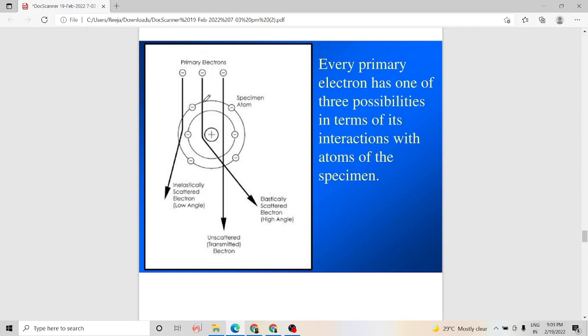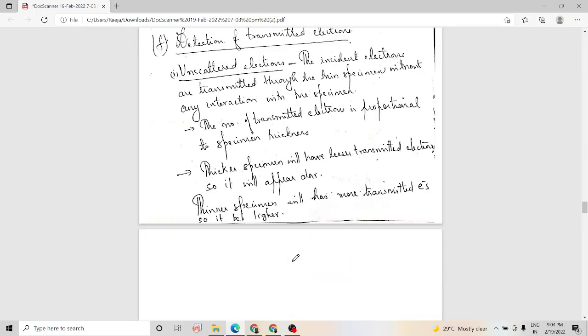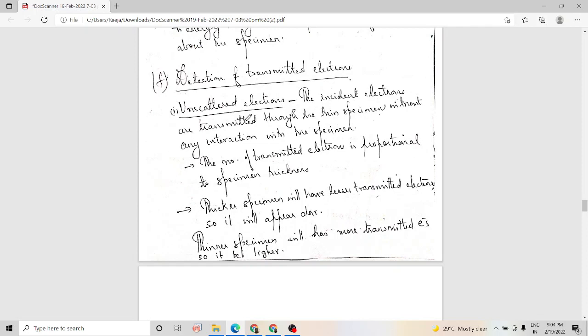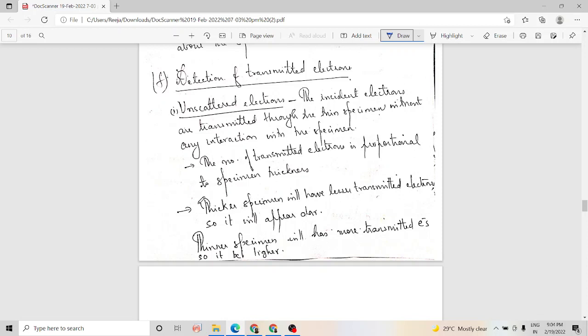Next, we discuss transmitted electrons. When the primary beam of electrons transmits through a specimen, it can go unscattered, elastically scattered, or inelastically scattered. In the first case — unscattered electrons — the incident electrons are transmitted through the thin specimen without any interaction. The number of transmitted electrons is proportional to specimen thickness: thicker specimens produce fewer transmitted electrons and a darker image, while thinner specimens allow more electrons through, giving a lighter image.